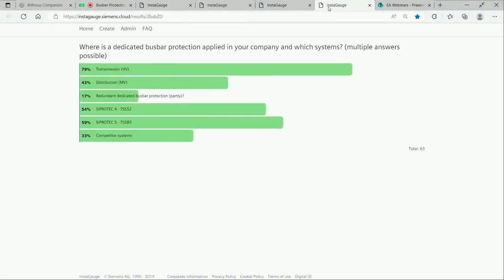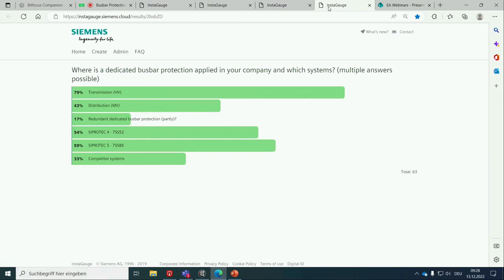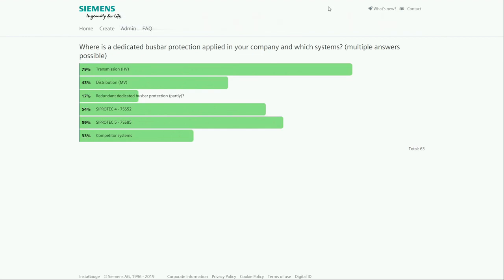Okay, I see Gert has already some results for me. So 80% say you need busbar protection in transmission. This is a very typical, traditional application for busbar protection. Of course, there are high voltages, high currents. Here, the real damage can happen. But already 40% of you say you use this busbar protection also in the distribution medium voltage environment.